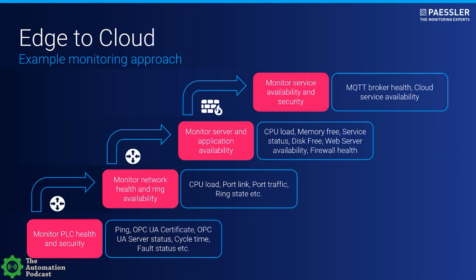Now when they have an issue, they can pinpoint exactly what the actual cause of the disruption was. They know, even by checking the single components inside the program logic, whether the actual port was opened by the PLC to the MQTT broker. They know if the network is working, if the MQTT broker is working, if the applications and the firewall in between work. So they can exactly pinpoint where the issue is coming from and what's actually going on.